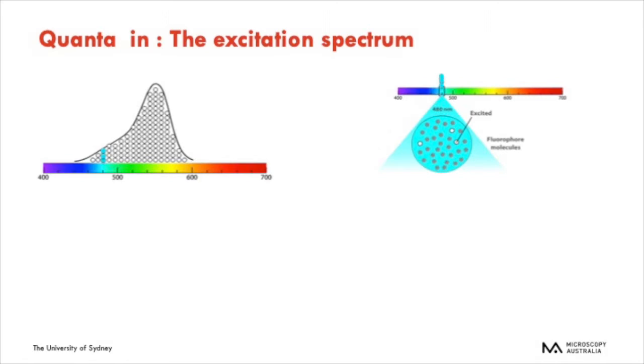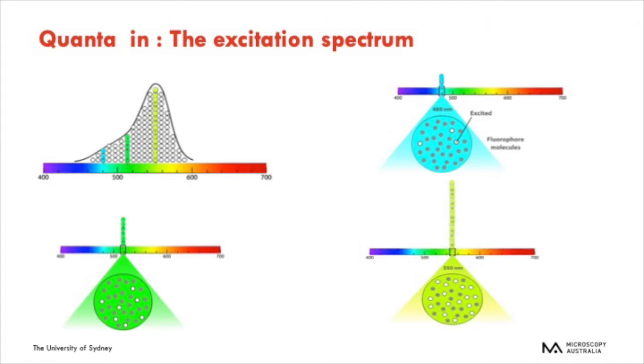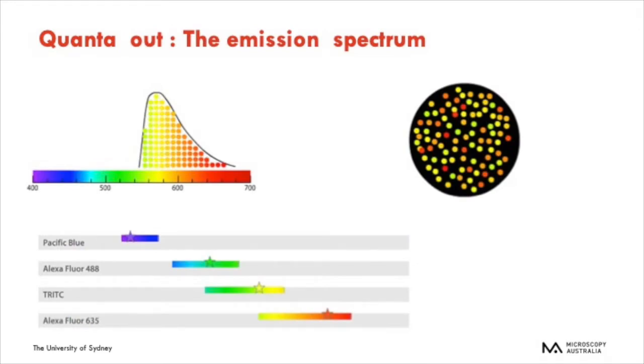Looking at the absorption curve for a specific molecule: if you excite at 480nm, only a few molecules are being excited. If you excite at 500nm, more molecules are excited. And at the maximum of 550nm, the most molecules are absorbing the light. Therefore, you really want to be exciting your molecule at its maximum absorbance, though this may not always be possible depending on the laser lines available to you. Looking at the emission curves of various dyes, they vary greatly. While the emission curve of a particular dye is always exactly the same regardless of where you excite it, different emissions mean we can label specimens with multiple probes and selectively collect the emission.